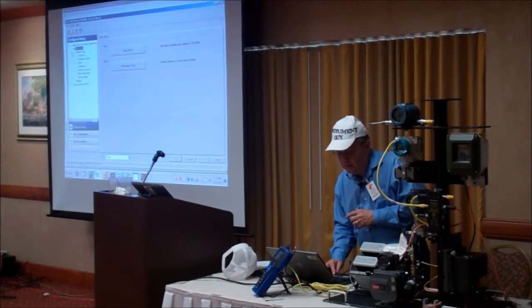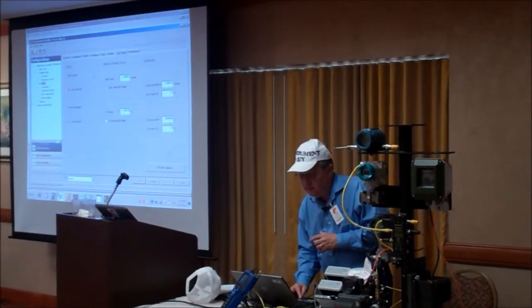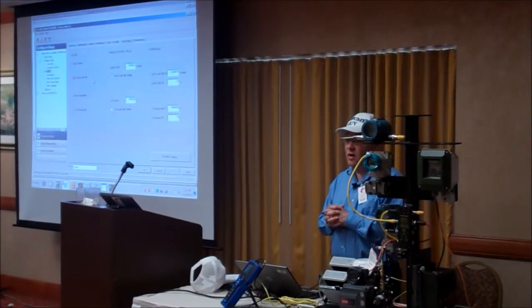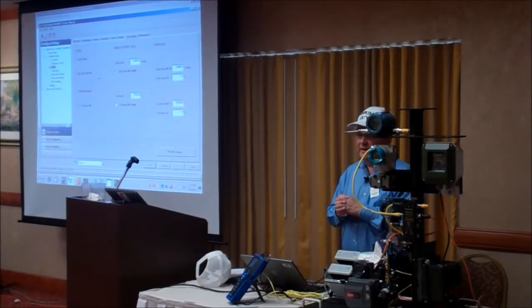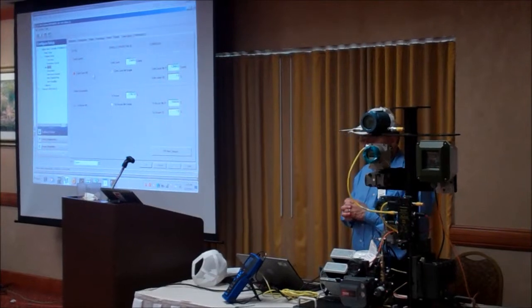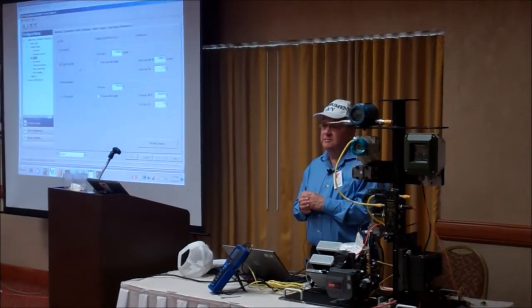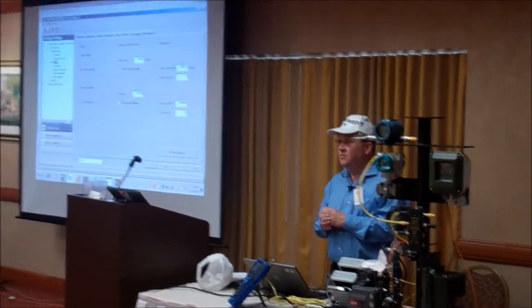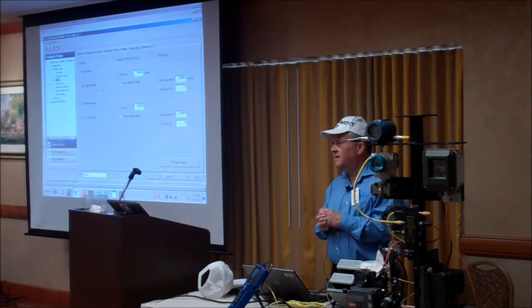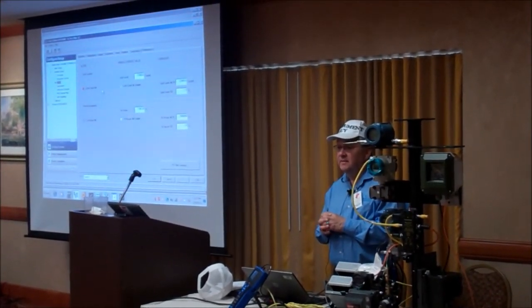So we'll call that up, alerts, travel history. Sure enough, there's a cycle count problem. So it's time for the maintenance guy to go out. Doesn't have to do it immediately, but that should be in his plan to go look at that valve pretty soon. Is this something that the operator needs to be concerned about right away? Maybe, maybe not. Probably not. Depends on the philosophy of the plant, but typically that's something for the maintenance guy.